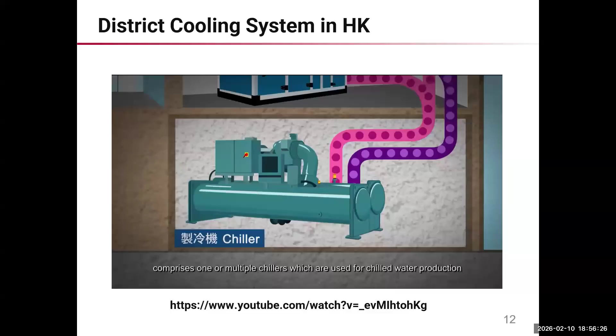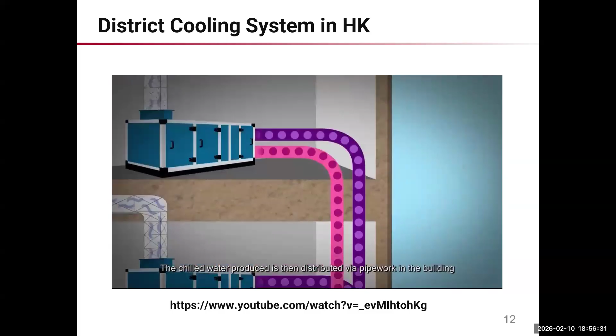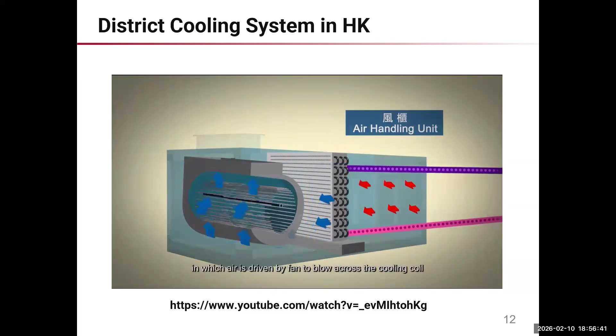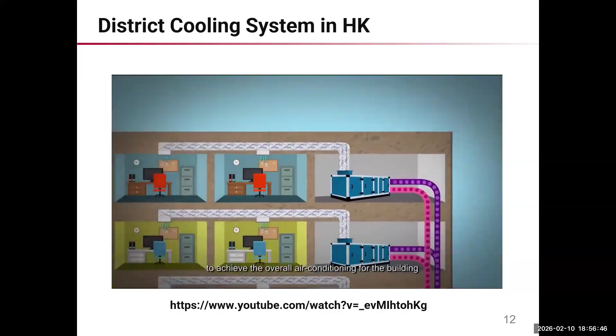A conventional centralized air conditioning system comprises one or multiple chillers used for chilled water production. The chilled water produced is then distributed via pipework in the building to the cooling coils of air handling equipment at individual spaces, where air is driven by a fan to blow across the cooling coil, and the cooled air is delivered into the space to achieve overall air conditioning for the building.